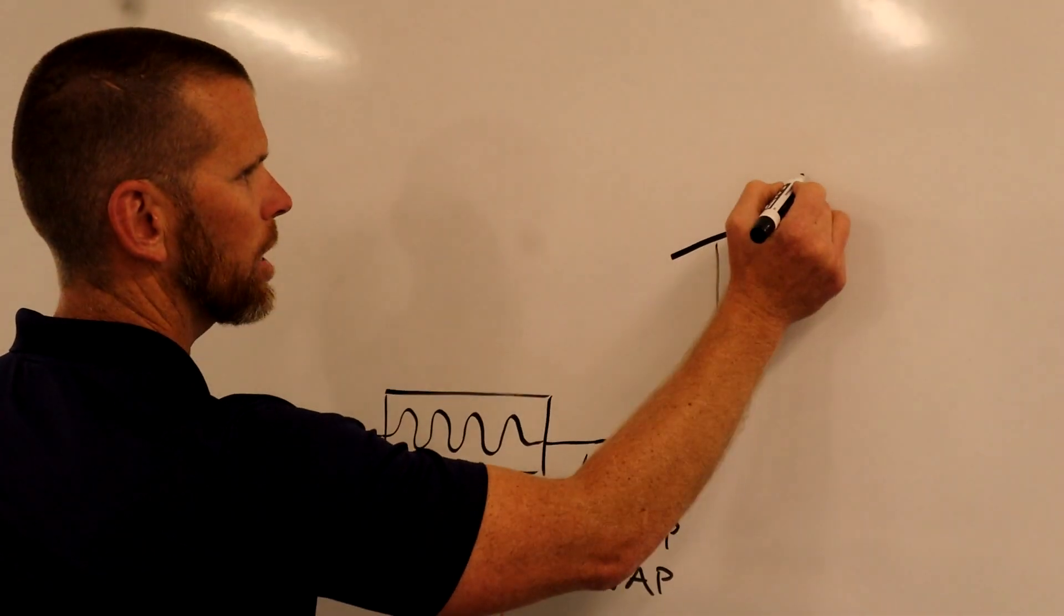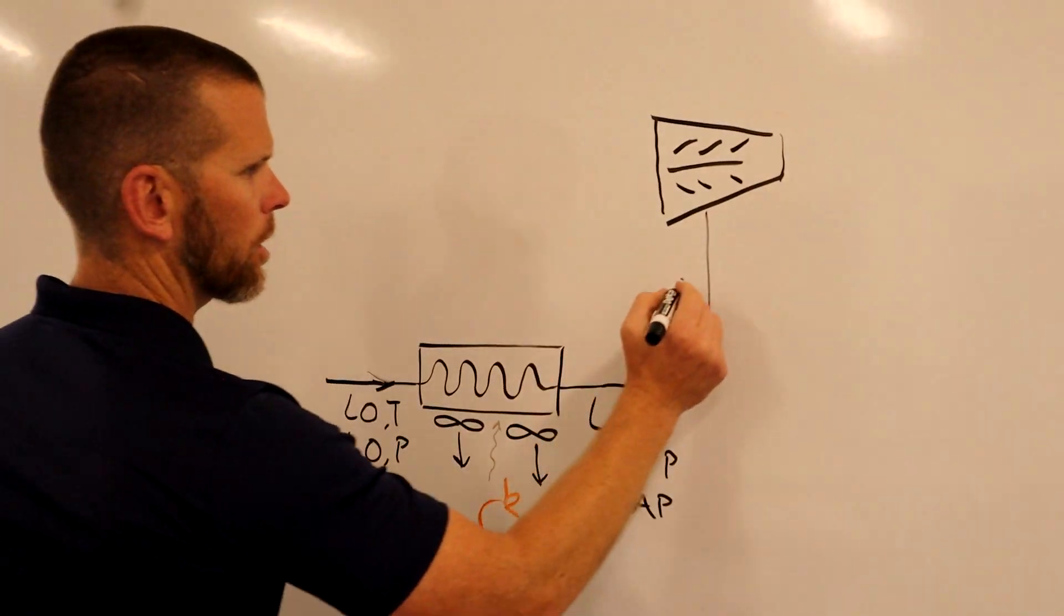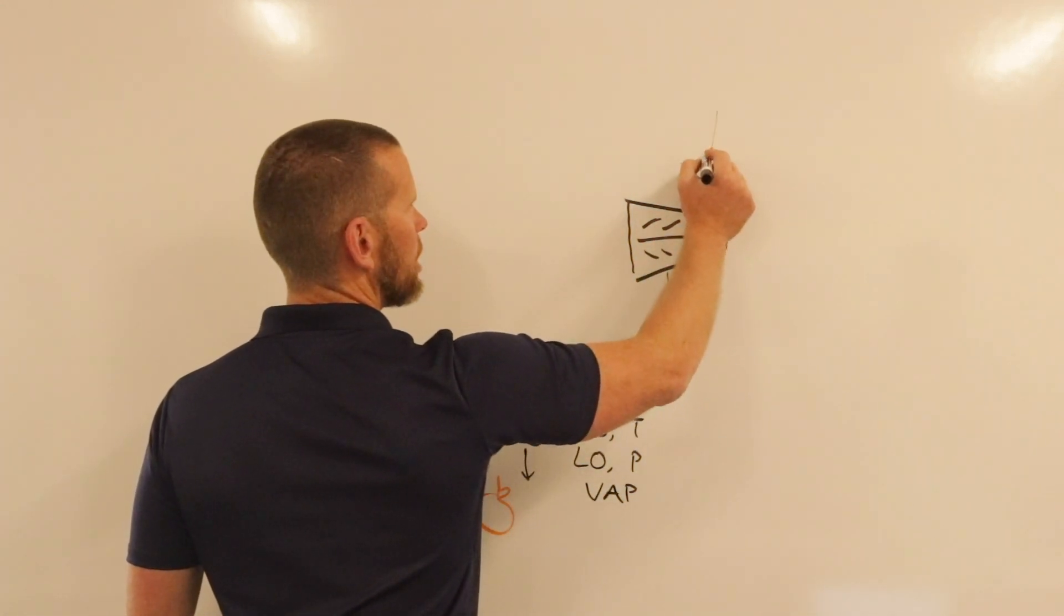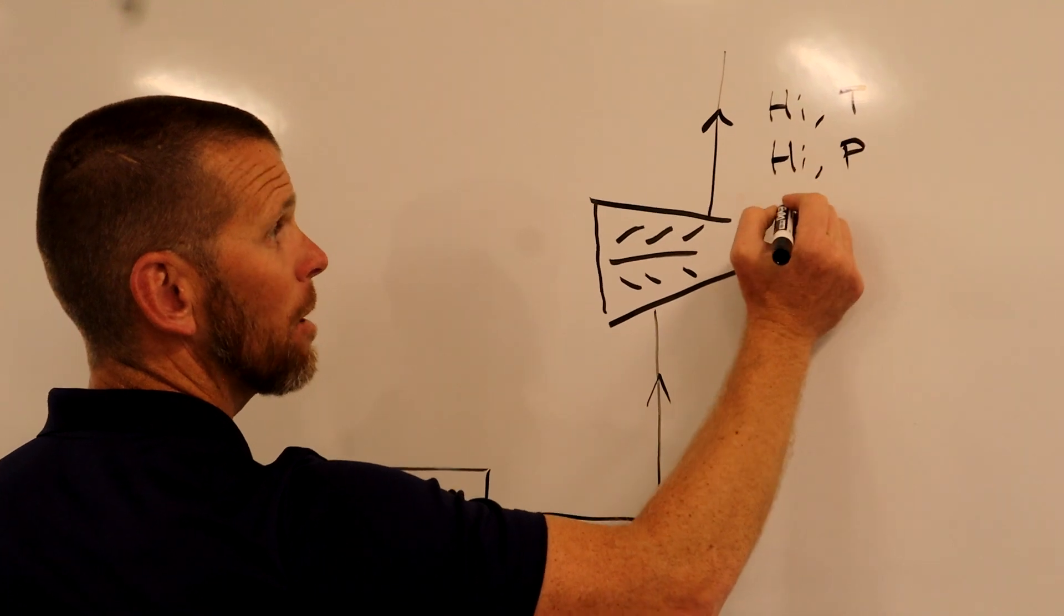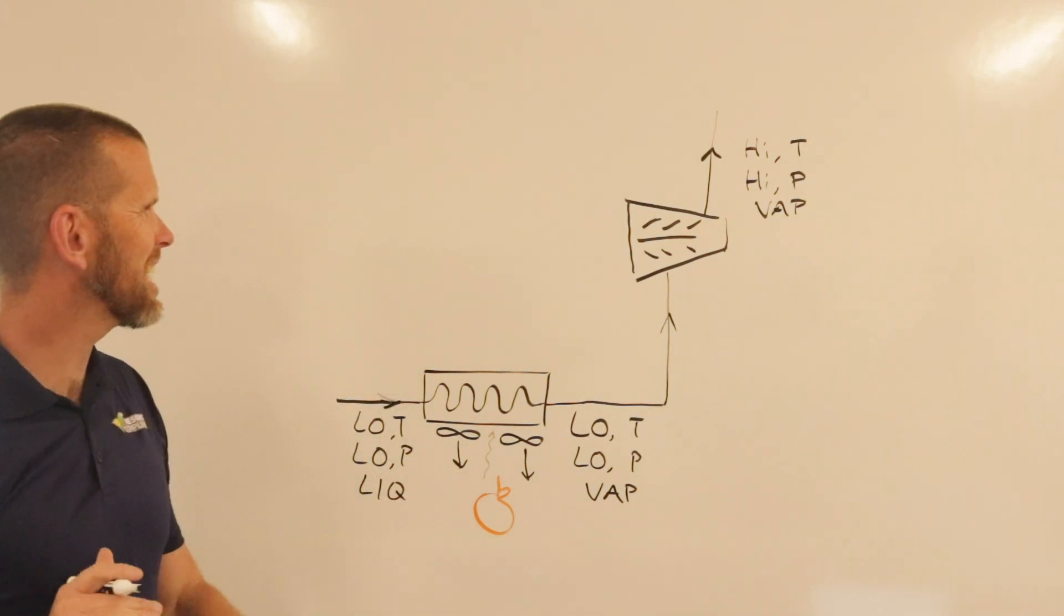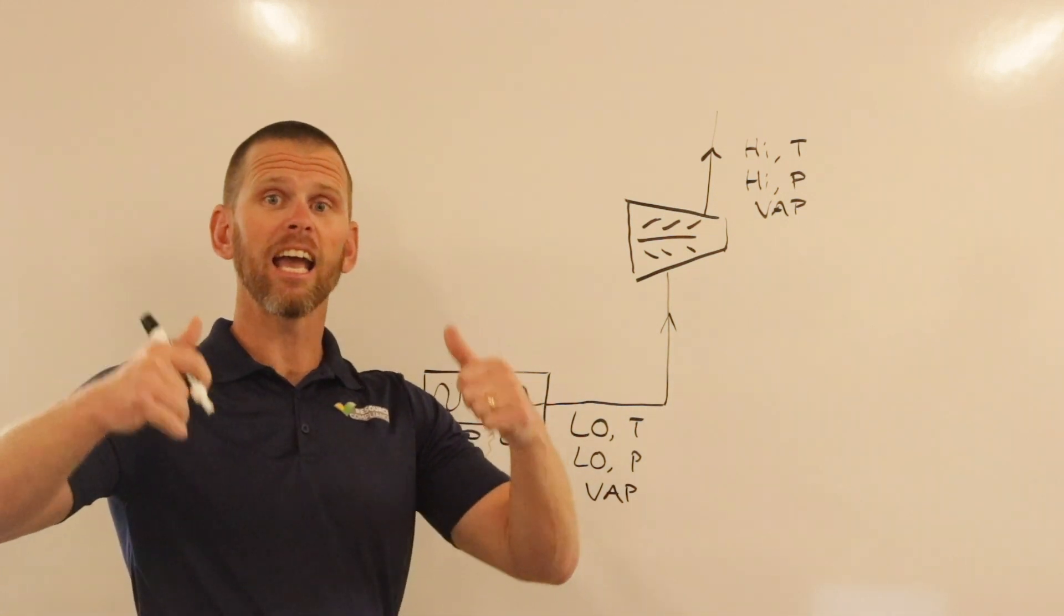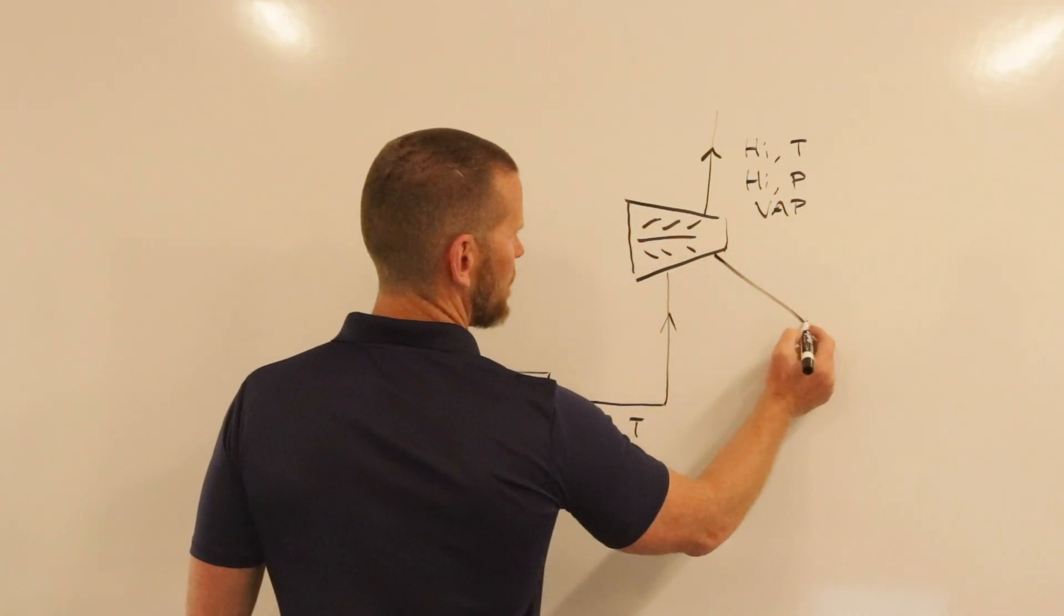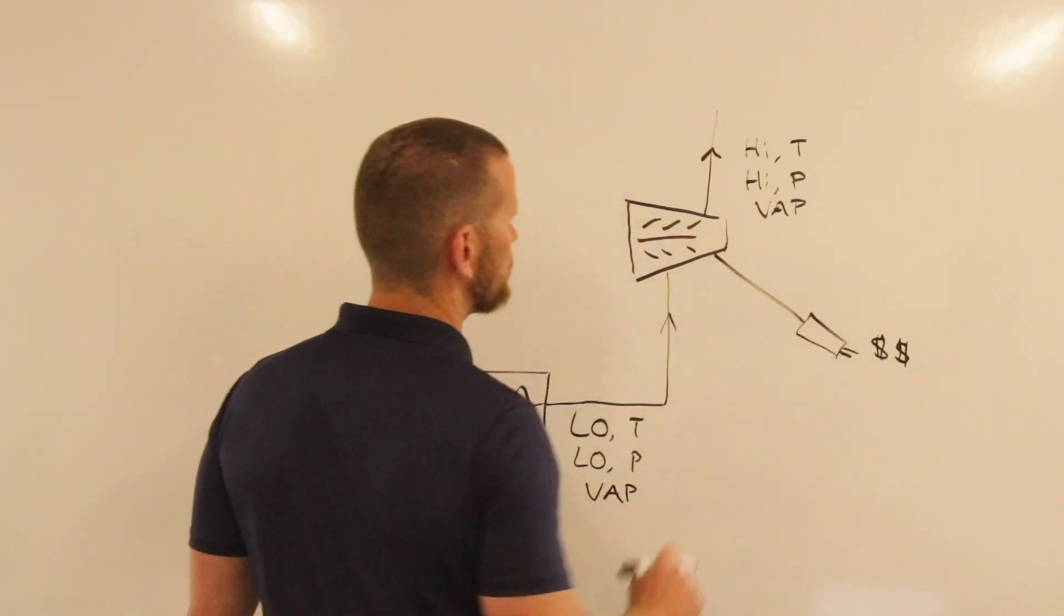We take it to a compressor. This low temperature, low pressure vapor enters the compressor and exits as high temperature, high pressure vapor. Remember, compressors hate liquids - no liquid should go through the compressor. We've taken our vapor and squeezed it down. In that process, the pressure increased and the temperature also increased. It's worth pointing out that this compressor requires a lot of energy - it's expensive to run this machine with a lot of horsepower.